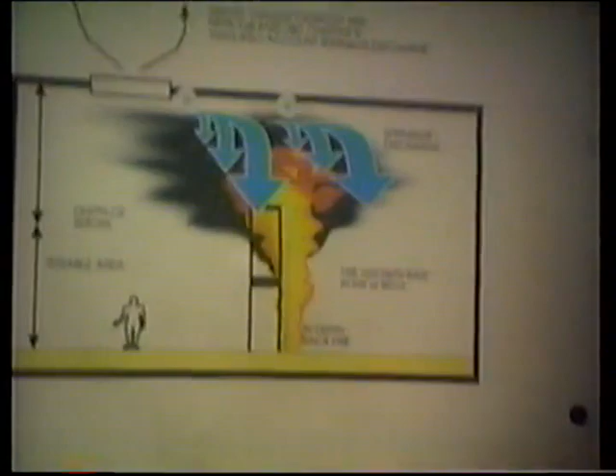Now, if you look at ESFR sprinklers, Factory Mutual says we don't want vents and draft curtains and stuff like that around our systems. It'll spoil them. And I think I'd take it a step further, because some of the fire test data suggests that we might want to look at that for all types of sprinkler systems. That's a hot one, because ventilation systems could screw up the performance in general of a sprinkler system. The jury's still out on that kind of data, but it takes this kind of technology to help us support some of this analysis.